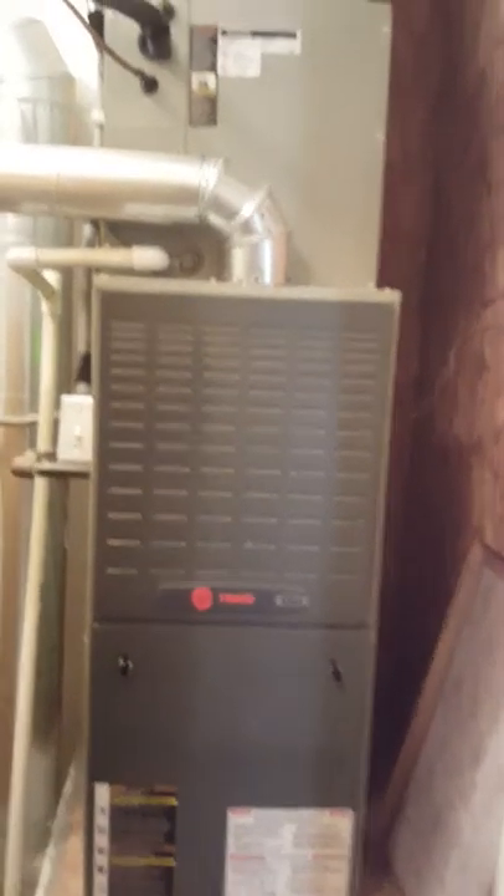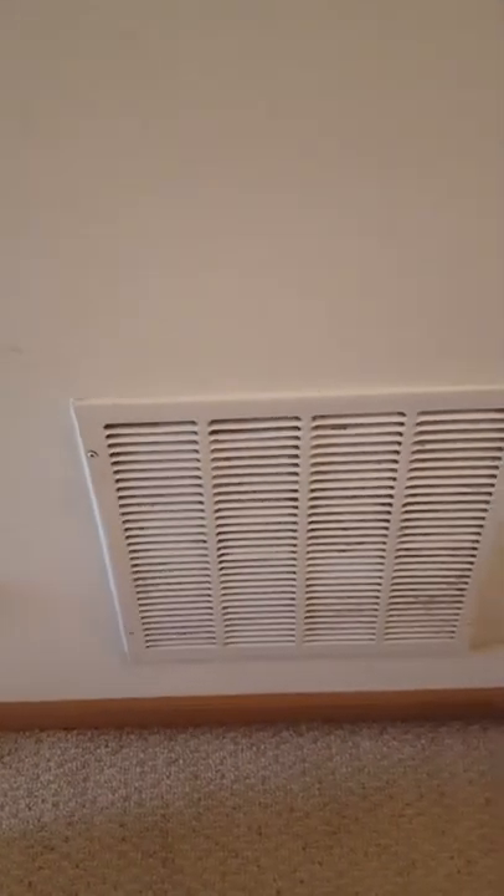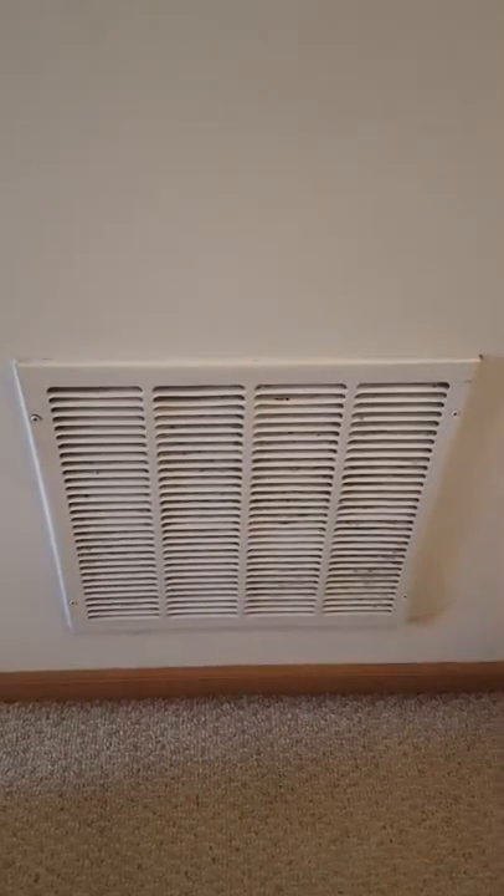Panning out to get the full look at the area here. It looks awful restrictive on the supply there — that way it's choked down there. And then also out here they're using a 16 by 25 by 1 filter inside the unit, laying on the floor of the unit.